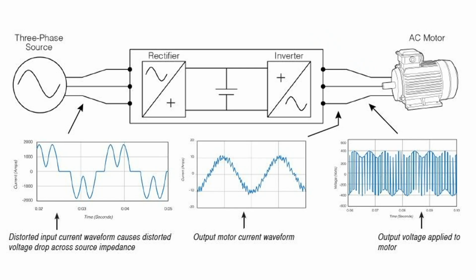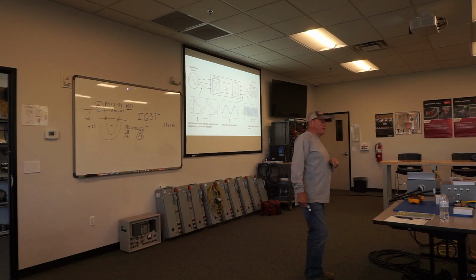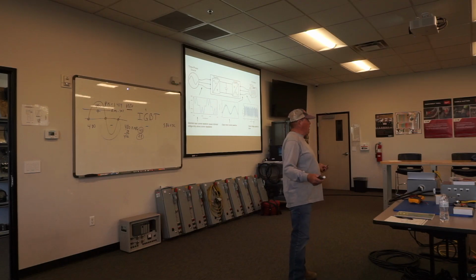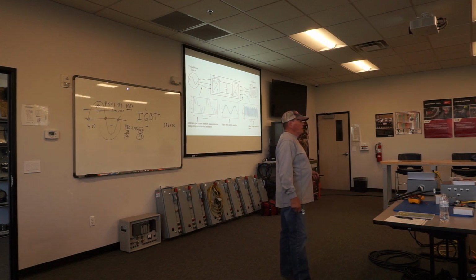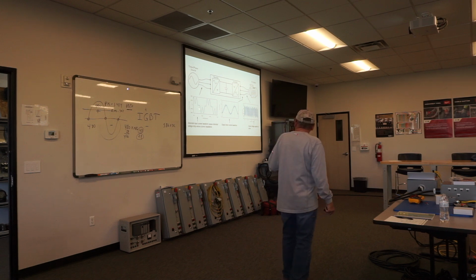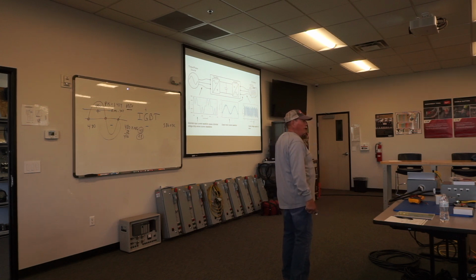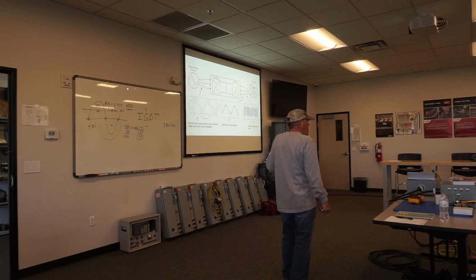So there's our distorted current sine wave that's being reflected off of this drive. So there's the start of creating dirty power onto the common bus. The common bus is everything on the switch gear feeding that building, because once it enters the switch gear from the utility, it's a common bus. The only thing separated is the 120/208 volt transformer. But everything on the 480 volt bus is affected by what starts off from the input side of the drive, creating dirty power. The more drives, the greater effect that has.